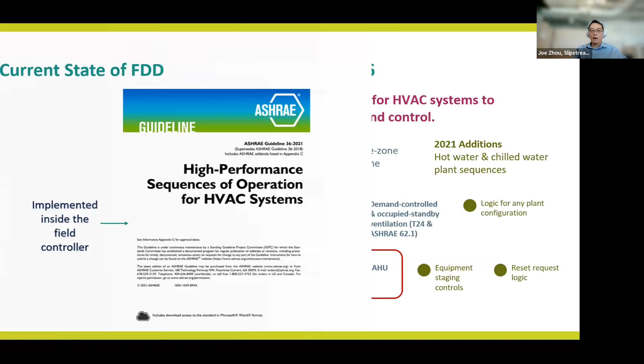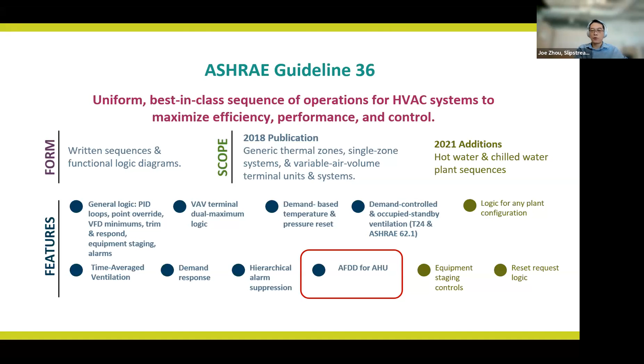I won't go through the detail. The guideline itself is a uniform, best-in-class sequence of operation for HVAC systems in order to maximize efficiency, performance, and controls. This lists the key measures for saving energy, but I will focus on the AFDD parts only in today's discussion. I only show one table. There are 15 rules, or they call them fault conditions, in ASHRAE Guideline 36. This is just the first condition, to give you an example.